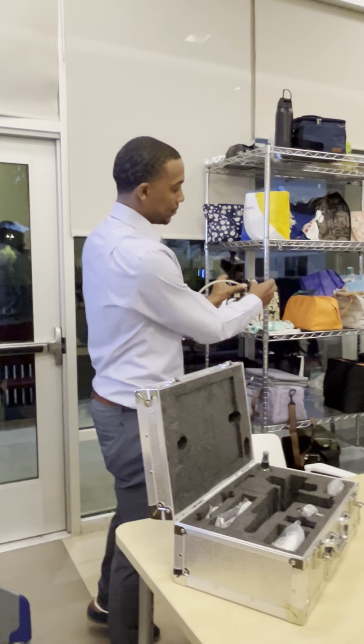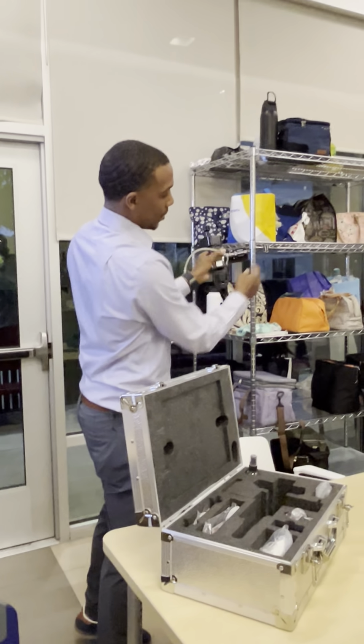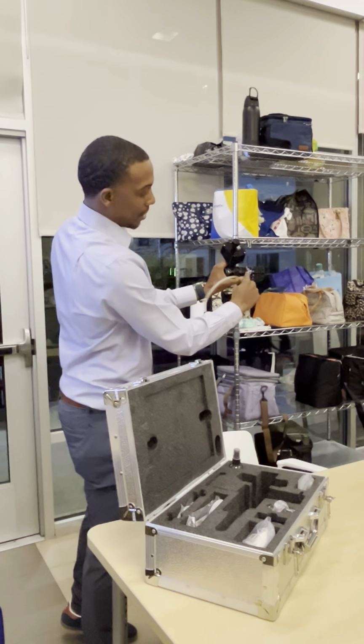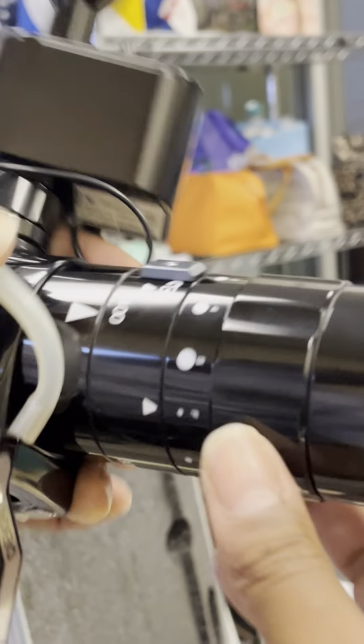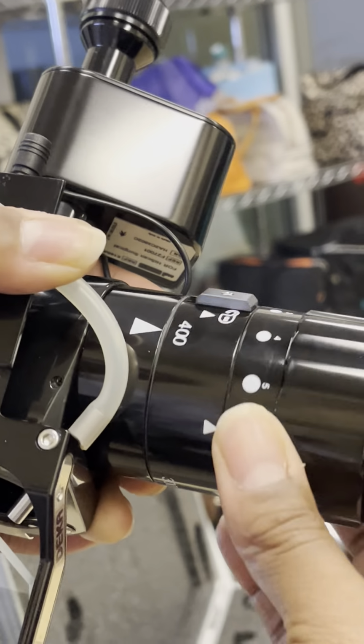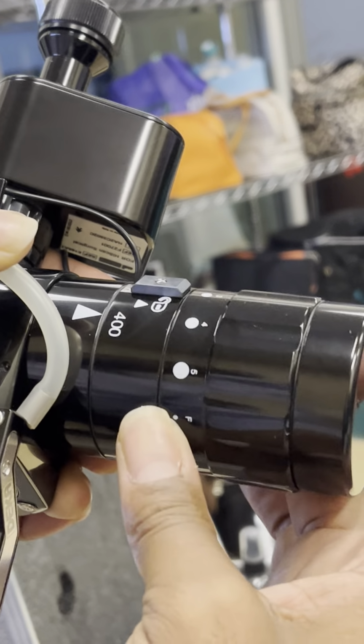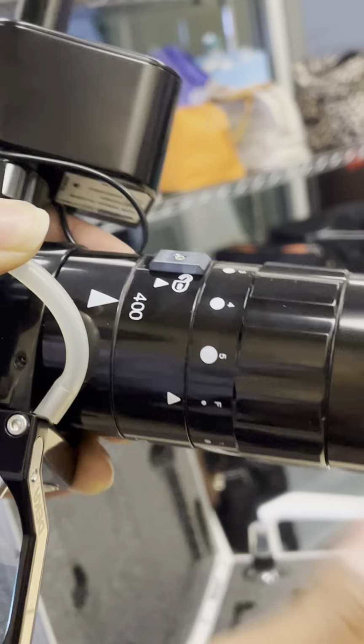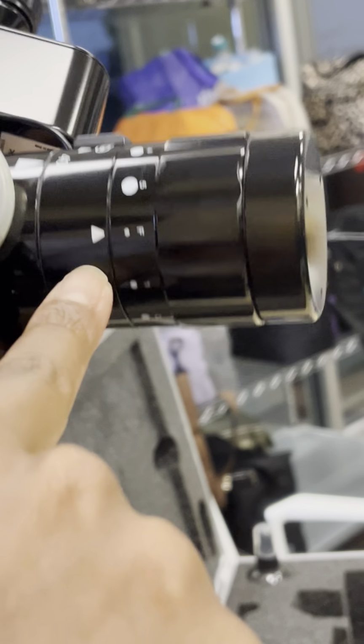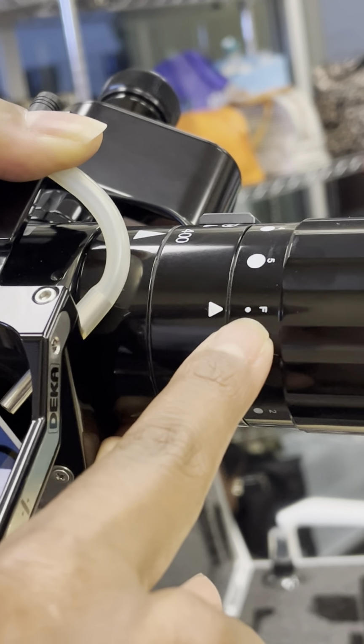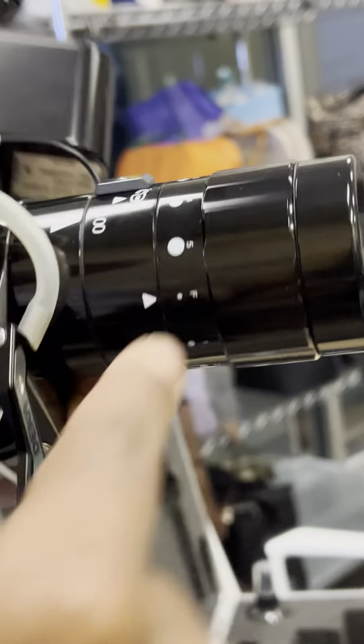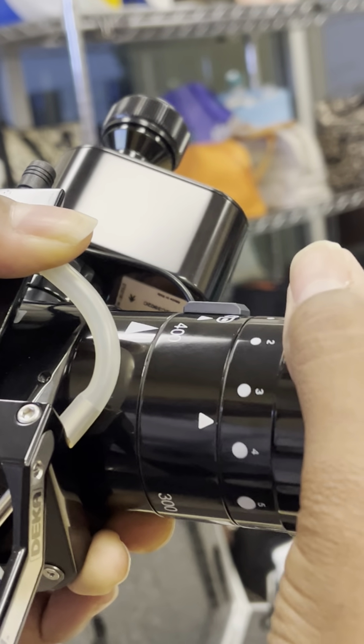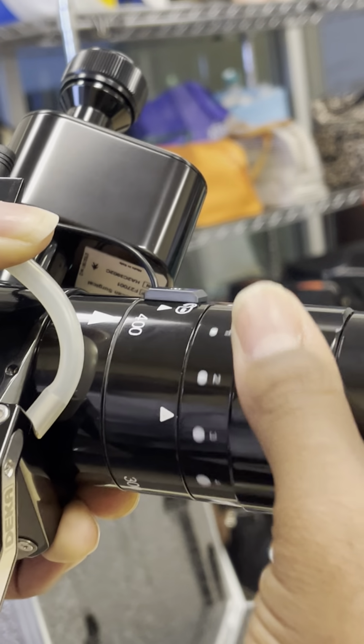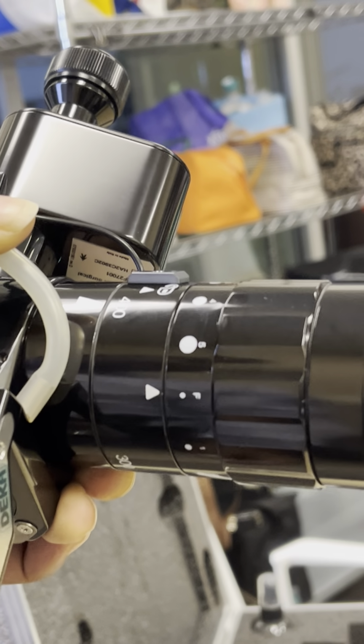Once you get that, you have to set your Microman. You have one major arrow up top. I'll get close to you so you can see it. You have one major arrow up top. In order to move the entire thing to get to that 400, okay, got it 400 now, you have to unlock it. In order to unlock it, you have to be on fine focus. Once you're in place, you can lock it. Now you can use your defocusing ring, and this is what the doctors will use to ablate.